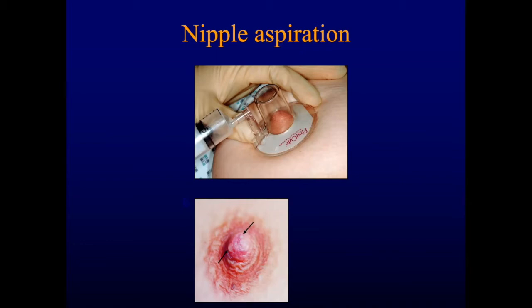In order to identify the ducts, the simplest way of doing that is to either massage or manipulate, but often, especially in postmenopausal women, it doesn't work. And you need some kind of aspiration device to be able to suck on the nipples to get some fluid to appear. So you can see here, the nipple aspiration cup is a very simple device. It's got a docking station to allow a simple syringe to be applied. You pull back 5-10 mils of negative pressure, and often you get a number of ducts, typically up to 4.